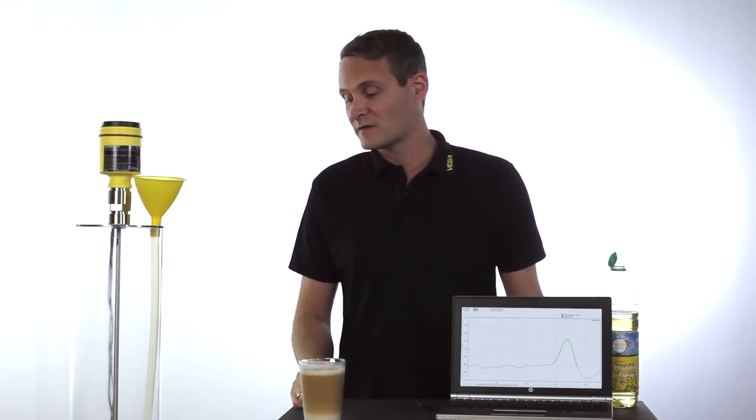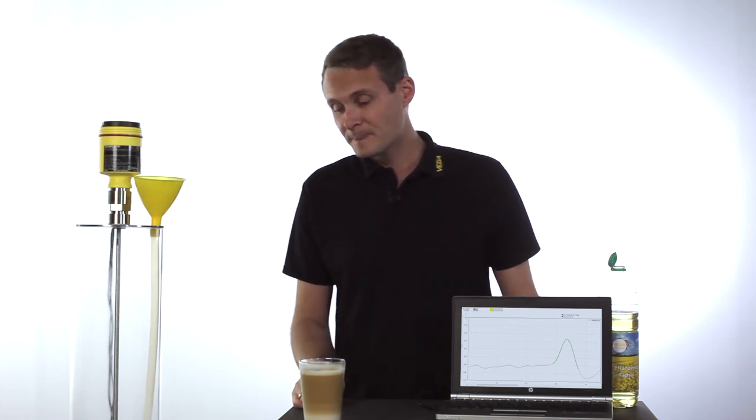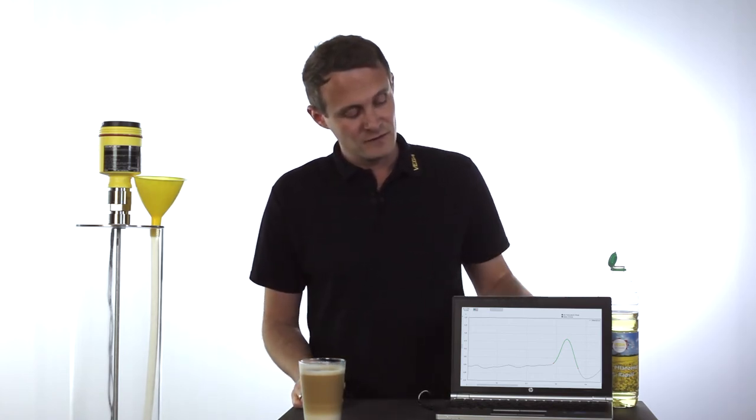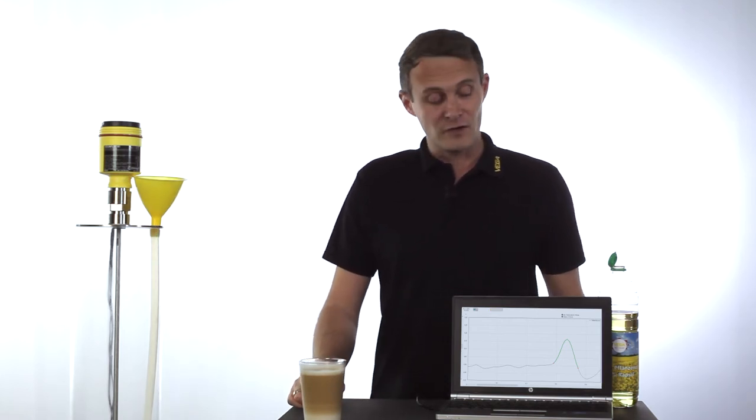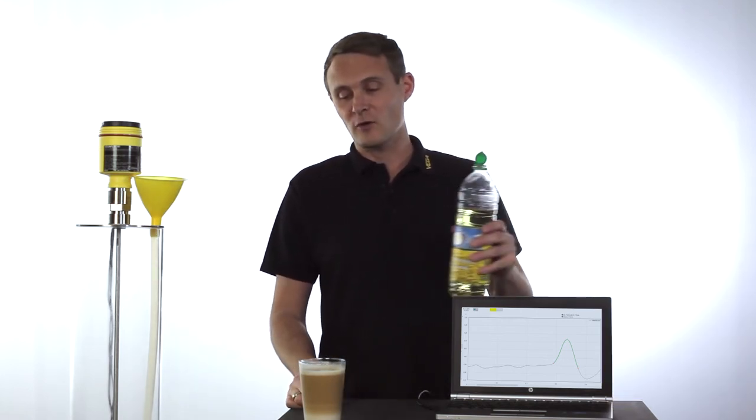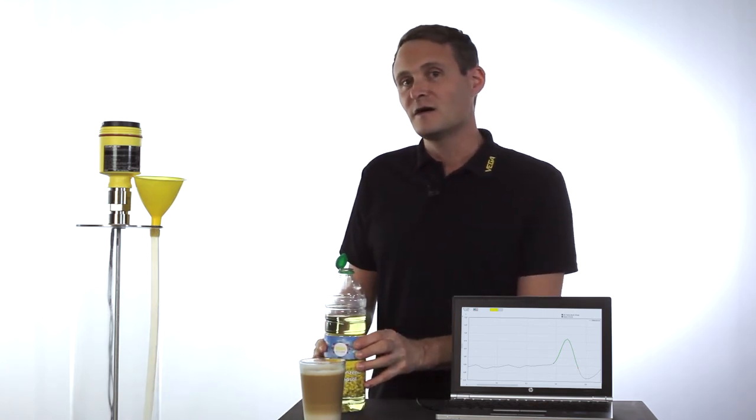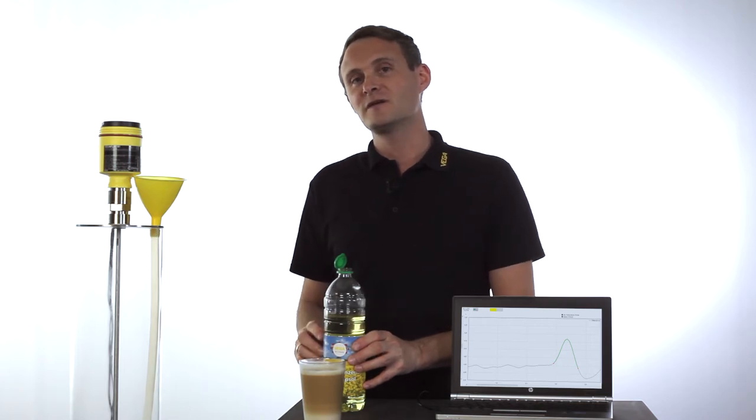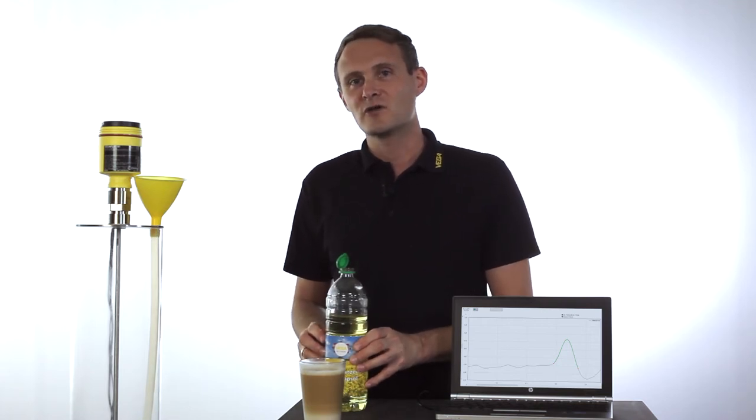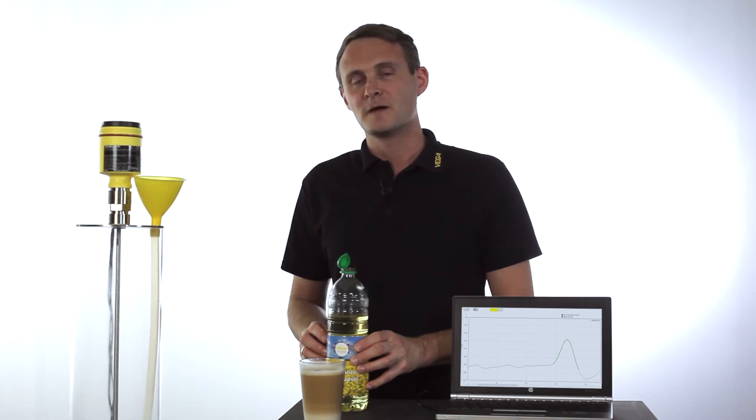At the moment this tank is just filled with water, and on the echo curve you can see the amplitude for the water level. We will now start to pour some oil into the tank additionally and see how thick the layer of oil has to be so that it can be distinguished from the water. Typically an oil layer of minimum 10 centimeters is necessary. Let's see how much oil we need for the VegaFlex 80.